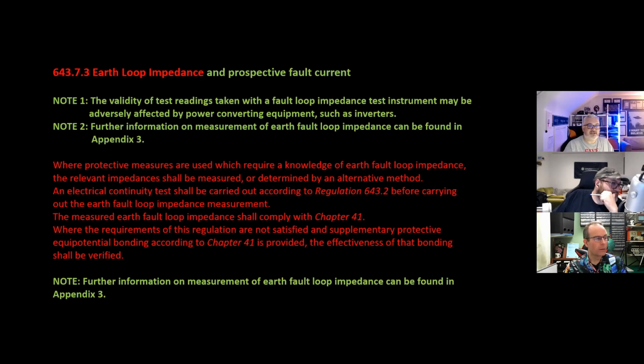There is then this section here where protective measures are used. That's existing information, so there's no change there. They then added a note: further information on measurement of earth loop impedance can be found... Why have I repeated that? Sorry, there's another mistake. Apologies. That's the exact same as note 2. I don't know why that's like that. That's my bad. But yeah, it's just a couple of additional notes, basically giving you a warning about affecting earth loops. But the key thing is earth loop impedance and prospective fault current. That's now telling us to test for fault current values.